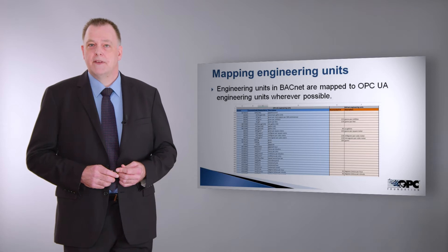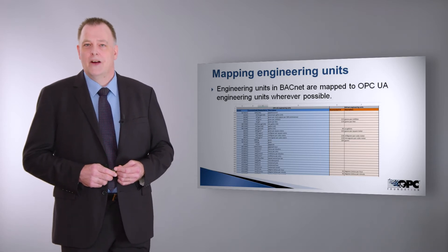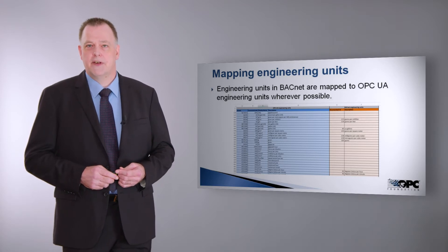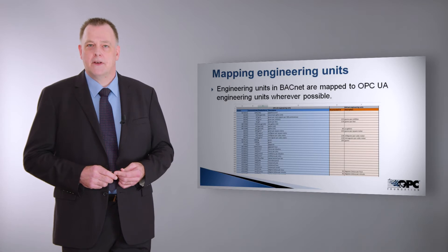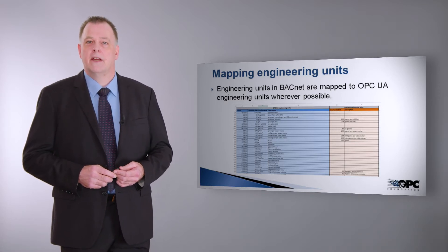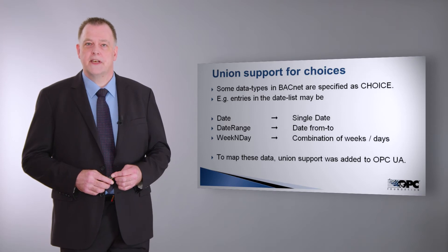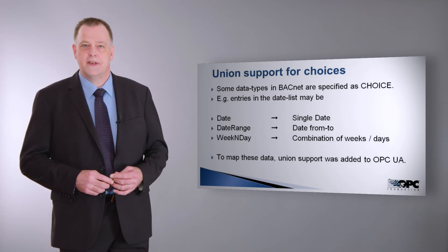Mapping the engineering units was a bit of a challenge. OPC UA has a total of more than 1300 engineering units, where BACnet only specifies about 200 engineering units. This table shows how the BACnet engineering units are mapped into the OPC UA engineering units using an Excel spreadsheet file. Some data points in BACnet are so-called choices — a choice may be a collection of different data types combined into a single one. For example, a date entry can be a single date, a date range, or a WeekNDay, which is a combination of weeks of the month and the days. This required OPC UA support for so-called unions, which allows mapping these BACnet choice data types into OPC UA unions.